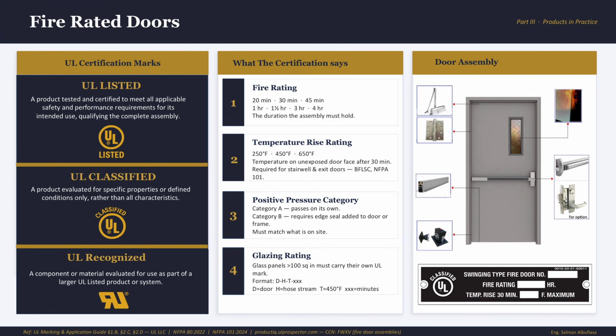UL has three different types of marks you need to know. First is UL listed, then UL classified, and then UL recognized. First, UL listed. This is the most important mark. UL listed means the entire product was tested and meets UL safety requirements as a whole product. So think of it this way: the complete fire door assembly will be UL listed. It will be ready to install, tested together as one complete system.